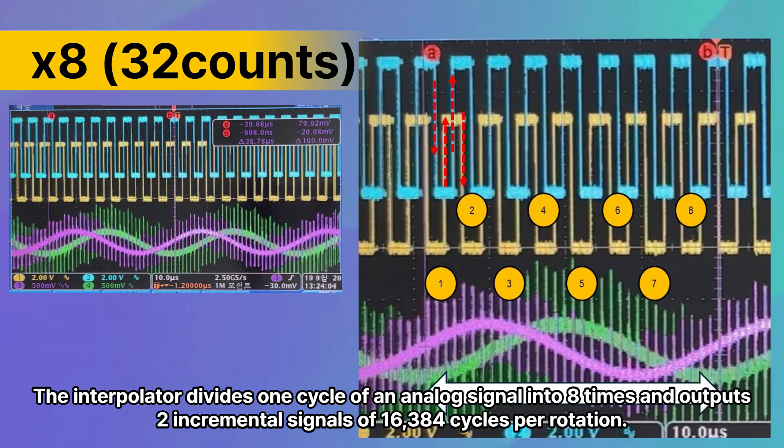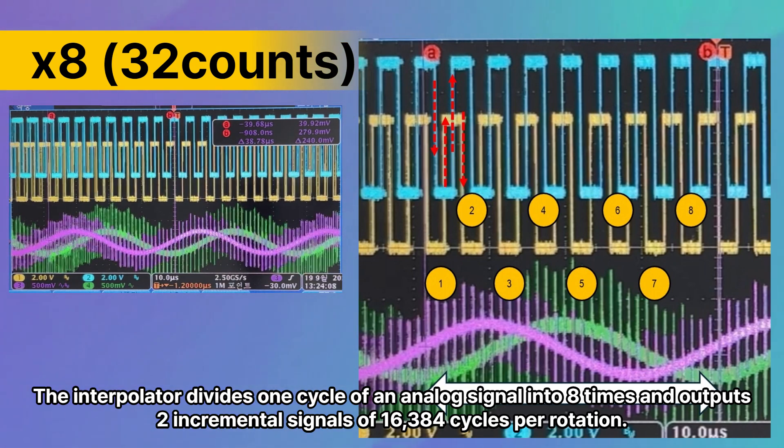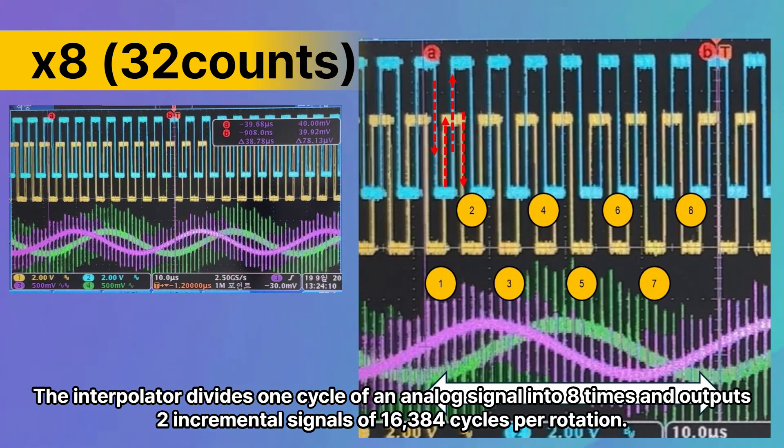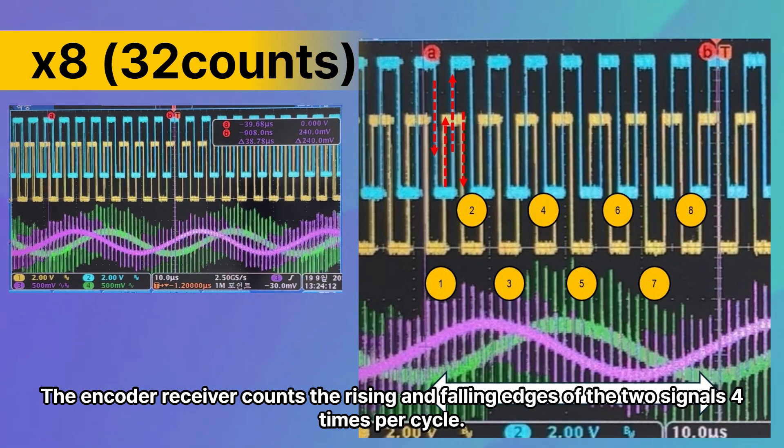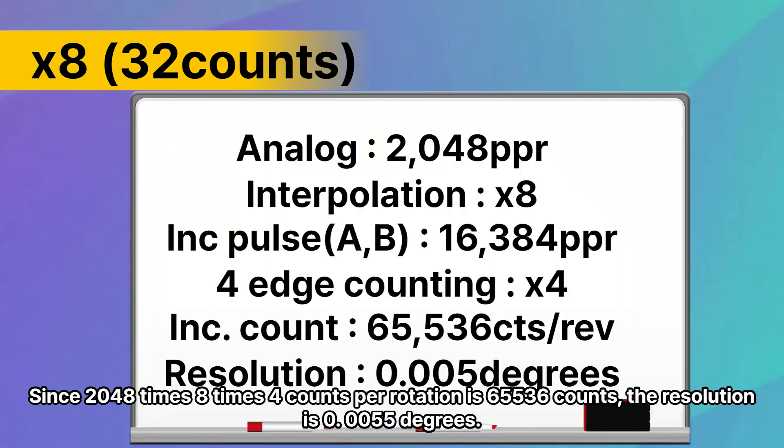The interpolator divides one cycle of an analog signal into eight times and outputs two incremental signals of 16,384 cycles per rotation. The encoder receiver counts the rising and falling edges of the two signals four times per cycle. Since 2048 times eight times four counts per rotation is 65,536 counts, the resolution is 0.0055 degrees.